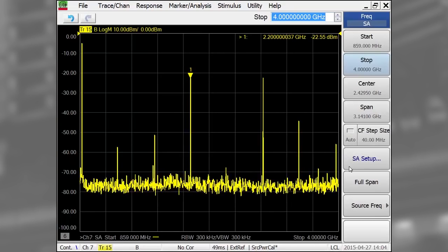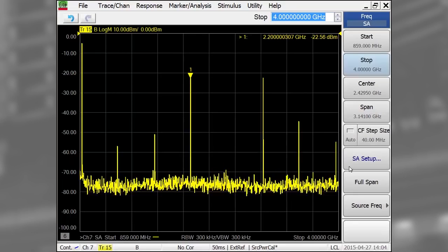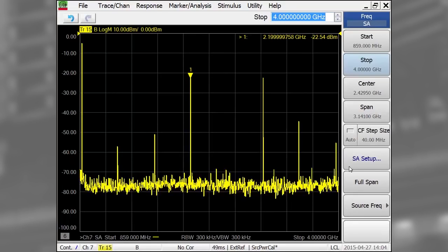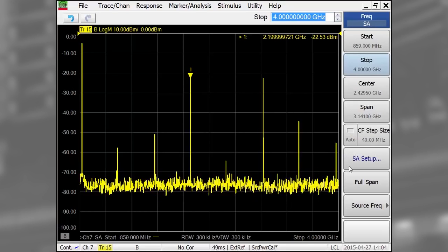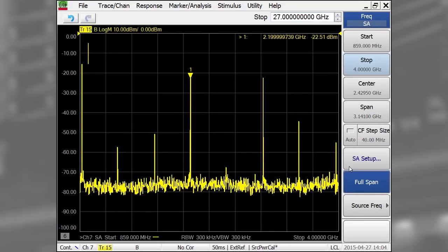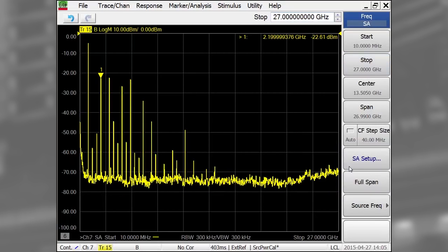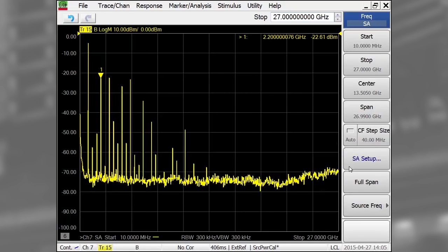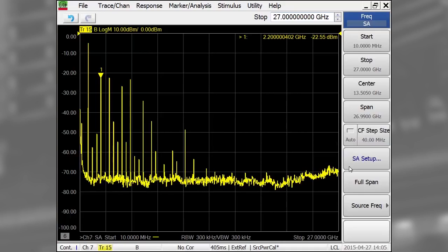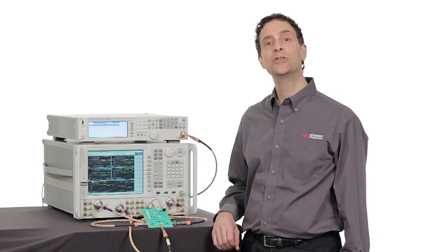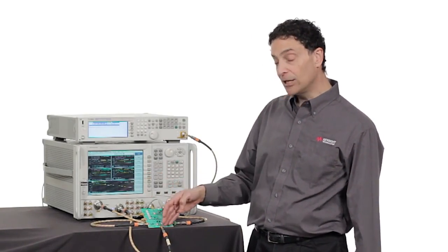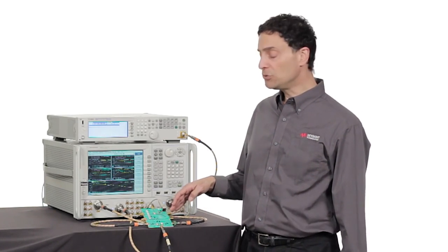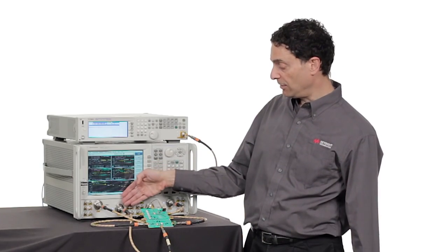That level of LO leakage is definitely too large for the noise receiver. It looks like there are other spurious signals coming out of the converter, so I'll press the full span soft key to look further out in frequency. Now I see the full range of spurious products coming out of the converter. I can also add measurements at the input and LO ports of the DUT by simply adding measurements using the test receivers at ports 1 and 3.